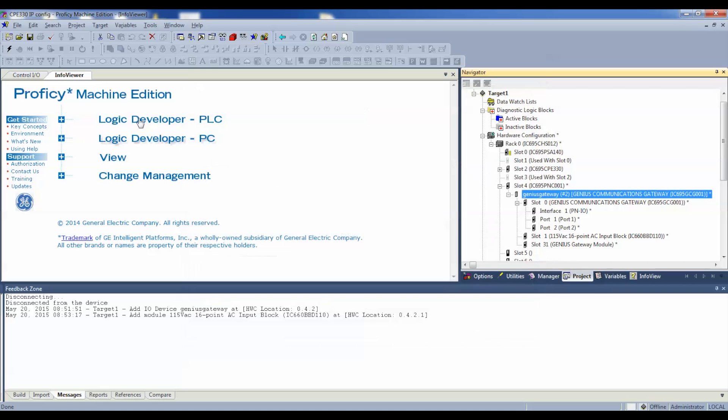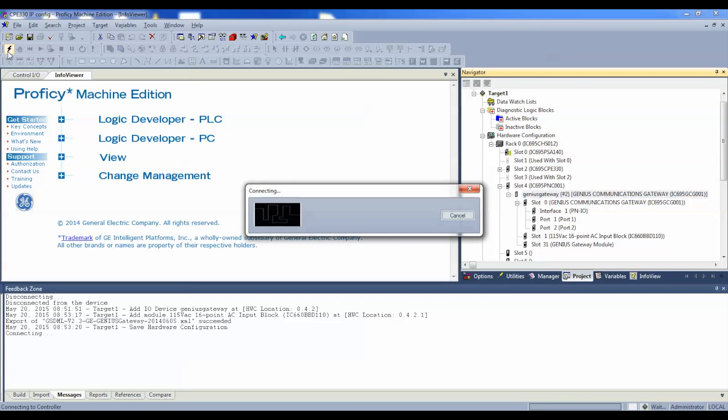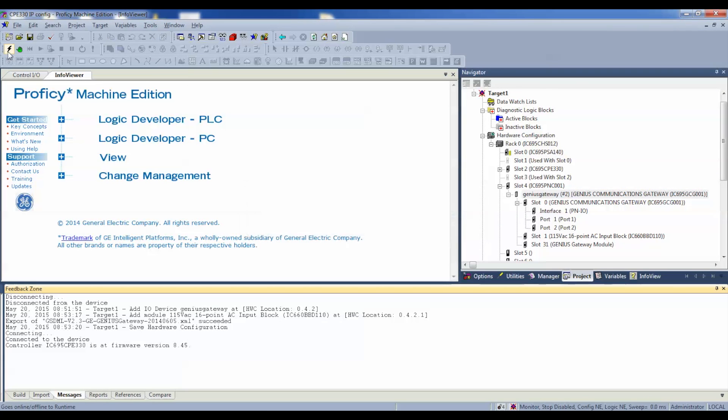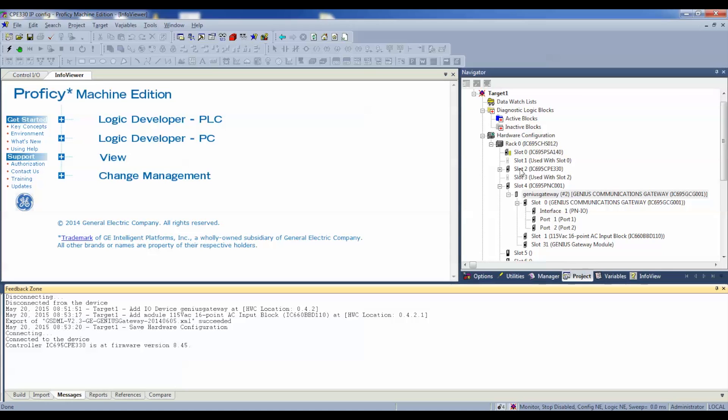And we're going to connect up to the controller. Now pay attention down below. I'm in monitor mode. It's stopped, disabled. That means that the processor is not in run mode, and that the inputs and outputs are disabled. Configuration and logic are not equal, because what's in the processor right now is not what's in front of me. So, we're going to need to do a download. I'm going to hit the hand print.